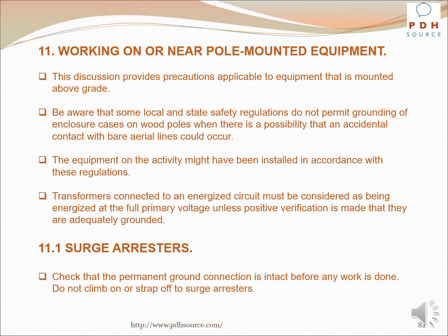Some comments on working on or near pole-mounted equipment. This discussion provides precautions applicable to equipment that is mounted above grade. Be aware that some local and state safety regulations do not permit grounding of enclosure cases on wood poles when there is a possibility that an accidental contact with bare aerial lines could occur. The equipment on the activity might have been installed in accordance with these regulations.